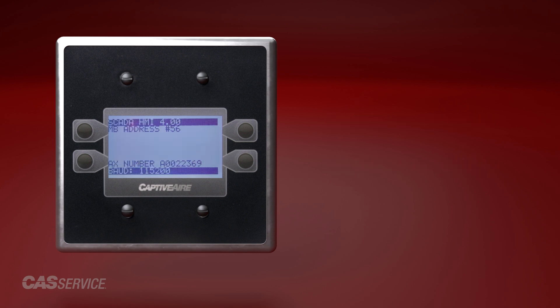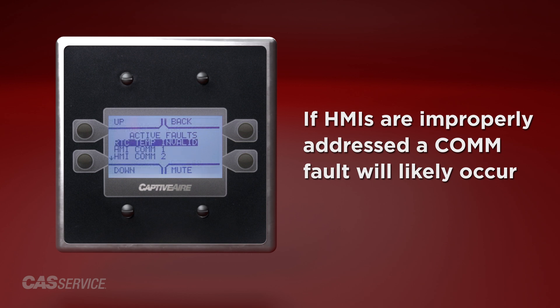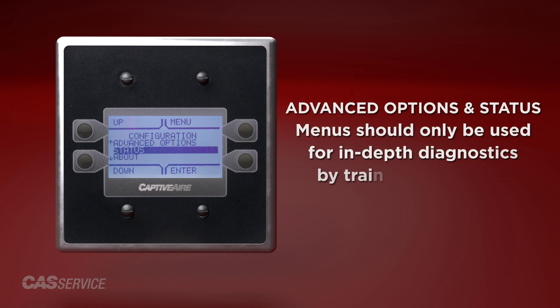It is not uncommon for space HMIs to get missed during the installation process, so this should be verified once installation is complete. If a unit is configured to have three HMIs and after applying power it displays an HMI COM3 fault, there is a good chance the space HMI that should be addressed as 57 is either not installed or not addressed accurately.